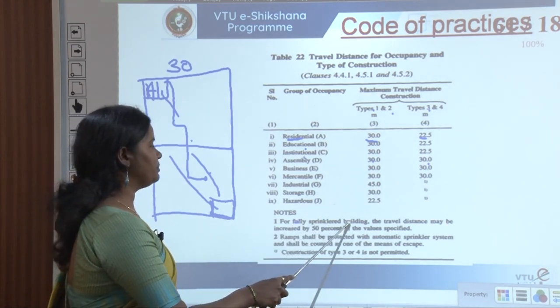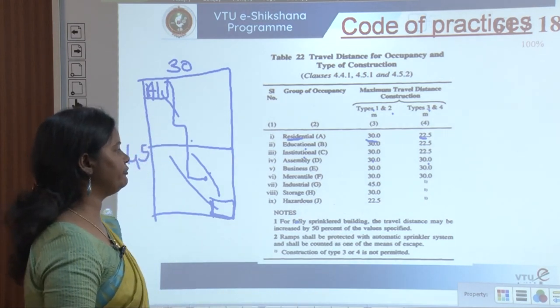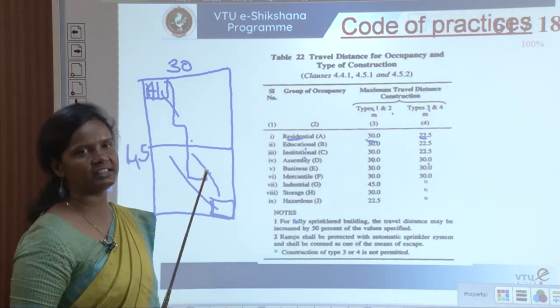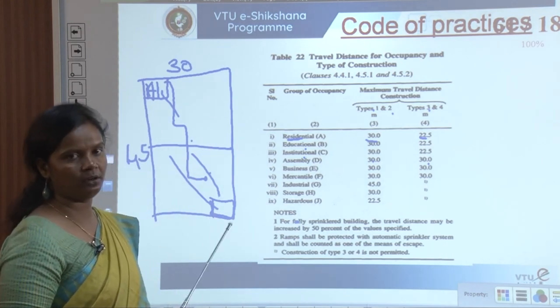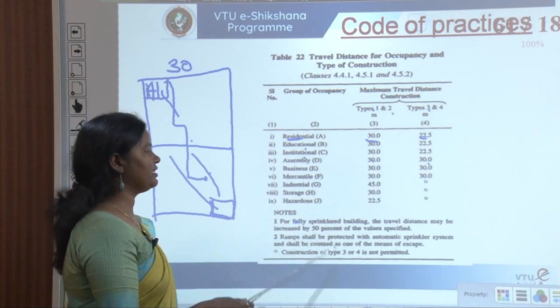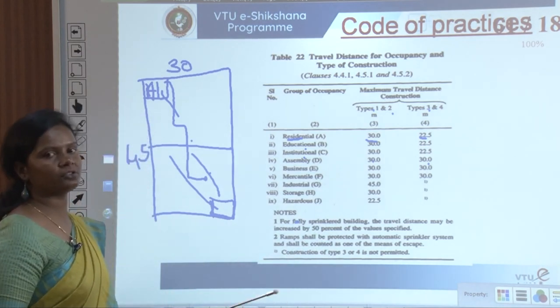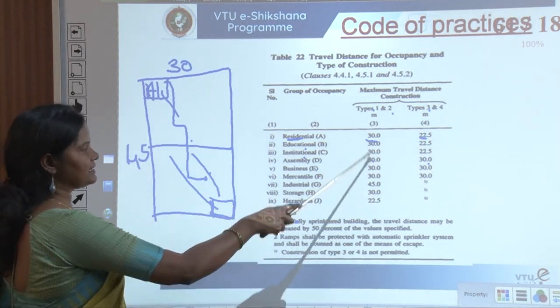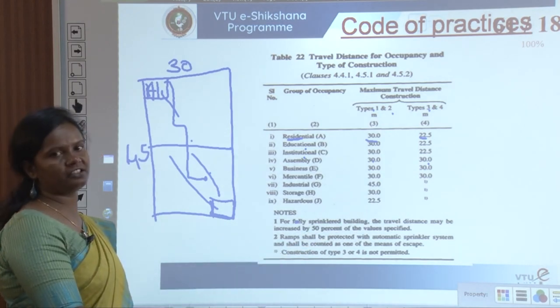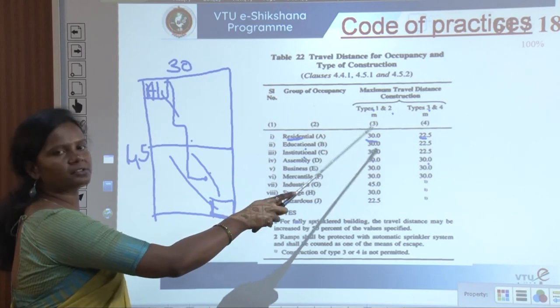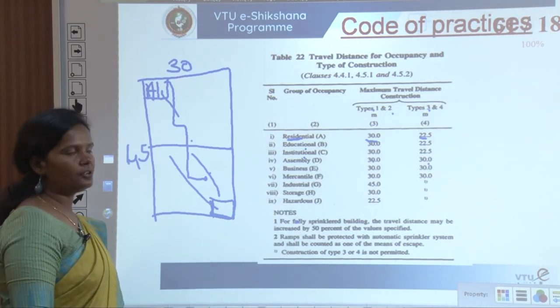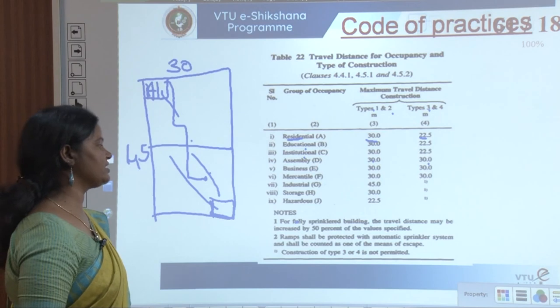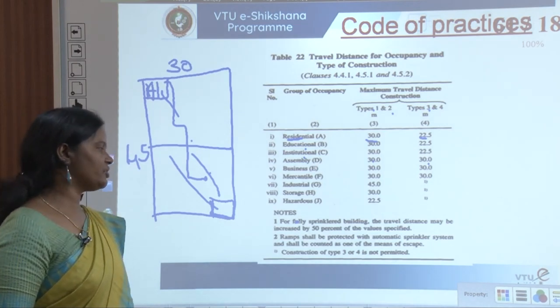For fully sprinklered buildings, the travel distance may be increased by 50 percent of the specified value — so 30 metres becomes 45 metres. This applies to buildings completely designed with a sprinkler system, not just fire extinguishers. Ramps shall be protected with automatic sprinkler systems and shall be counted as one of the means of escape.